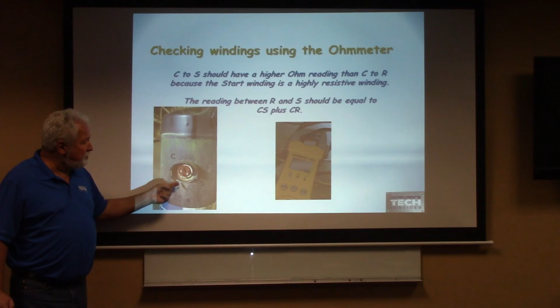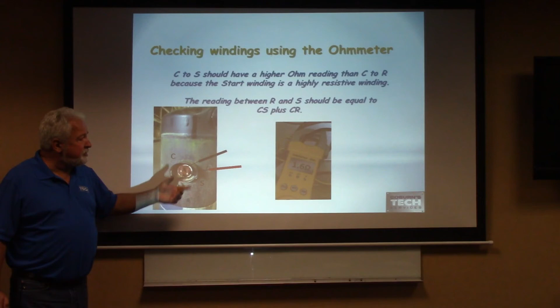Here's my common, here's my run, here's my start, there's my meter. If I put it on common and I put it on start, I might end up with 1.6 ohms. Everybody good? Good. I'll write that down somewhere over there. If I put it on common and run, I might end up with 0.6 ohms. Which one's the more resistive? The run or the start? Which one's more resistive? The start winding is a tighter wound winding. It's real tight and it's going to have a lot more resistance in it than our run winding will. Okay, so it proved that out.